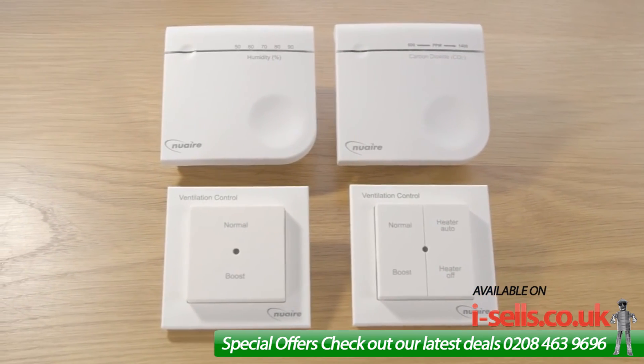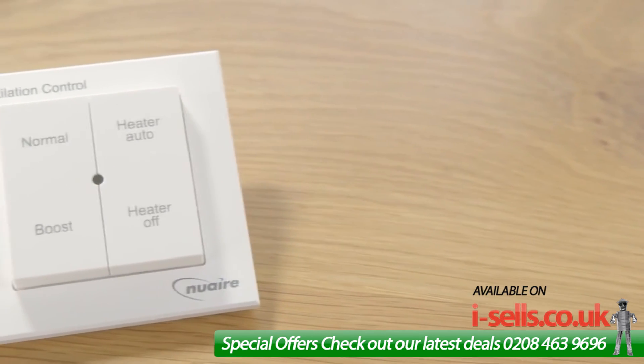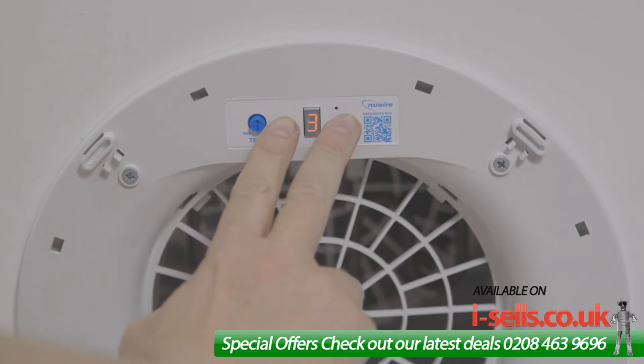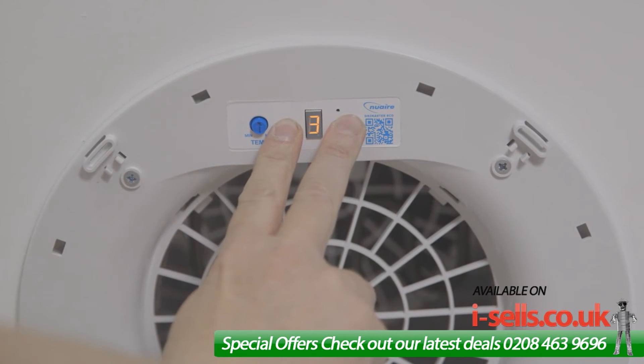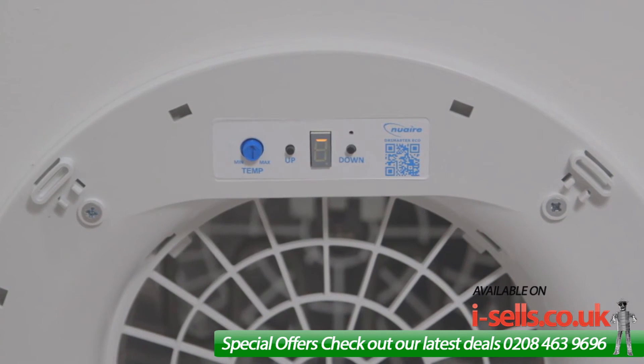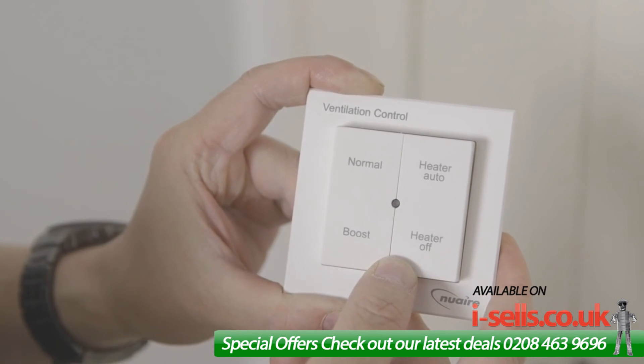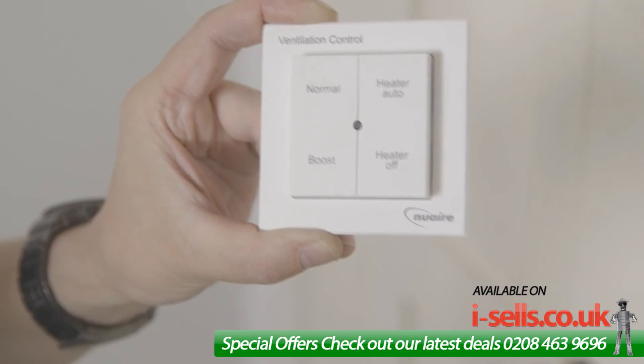Remote switches are available to provide the occupant control over their own comfort within the home. For this unit, I'm going to install a 4-way switch, which will require binding to the Drimaster Eco unit. Press and hold both up and down buttons on the diffuser for 20 to 30 seconds, then release. A single horizontal bar will now flash on the display — press the down button to enter binding mode. The display will flash B to indicate it has entered binding mode, and this will indicate for 5 minutes. During these 5 minutes whilst in binding mode, press and hold the bottom two buttons on the 4-way switch at the same time until the LED flashes green twice. This indicates the switch is bound.